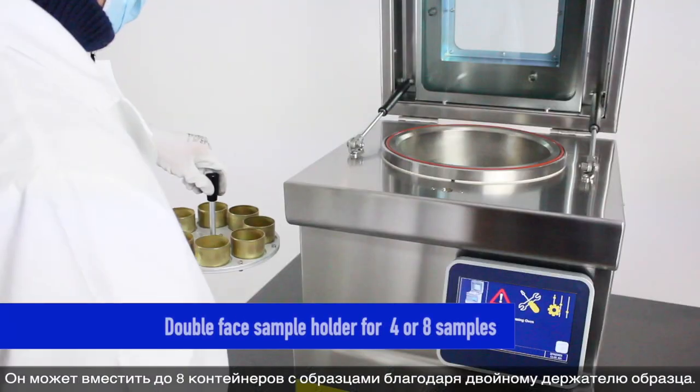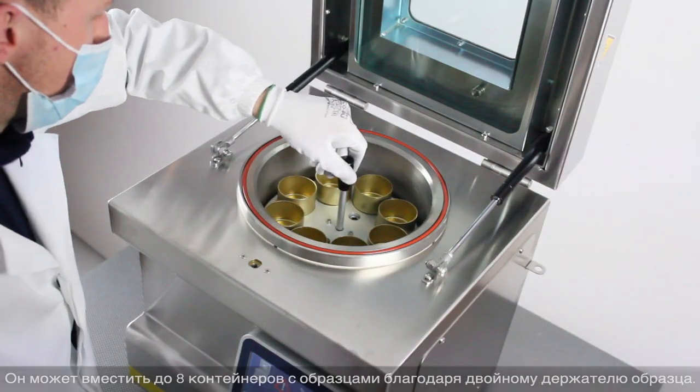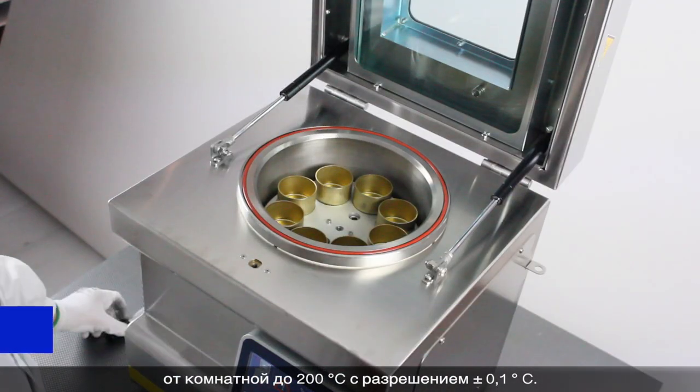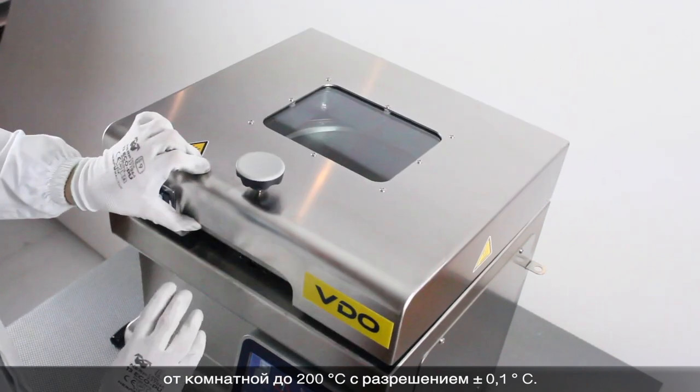It can hold up to eight specimen containers thanks to a double face sample holder. The unit allows a selective working temperature range from ambient to 200 degrees Celsius with a resolution of plus or minus 0.1 degrees Celsius.